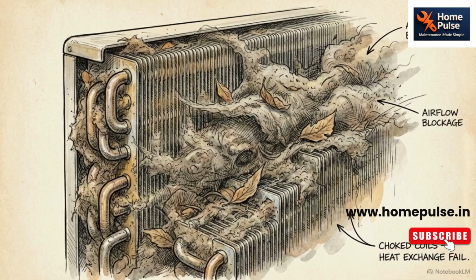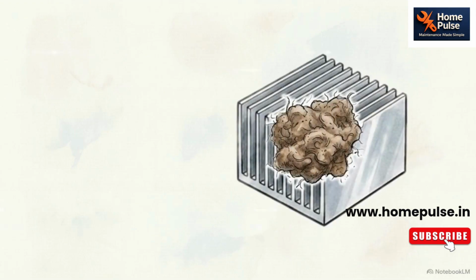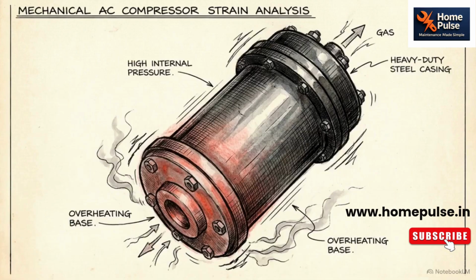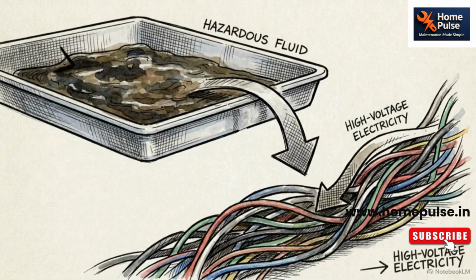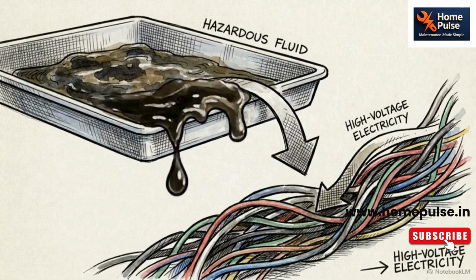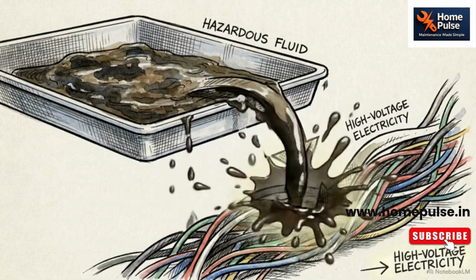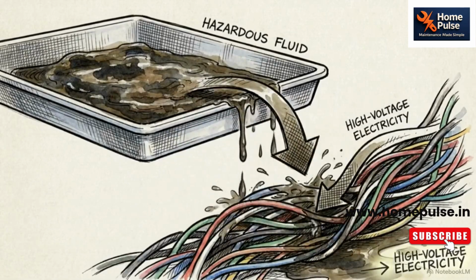Over months of running, thick layers of dust and debris silently accumulate across the outdoor condenser coils. This dust blocks the critical airflow needed to exhaust heat. To achieve the exact same room temperature, your compressor has to work much harder, running longer and running hotter. Inside, neglected maintenance leads to clogged drain pipes. The condensation backs up and starts dripping directly onto the indoor unit's electrical components.